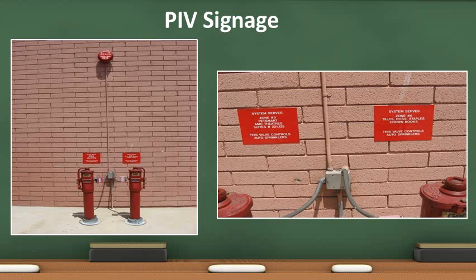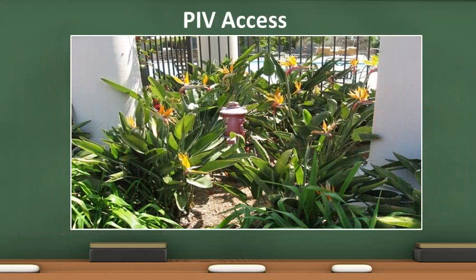In these photos, the signage indicating the buildings served is appropriately placed. Also note the sprinkler bell in the photo on the left. It is properly labeled with the type of alarm and instructions to call 911 when sounding. Note that three feet of clearance is required to all sprinkler system components. This PIV is obstructed and the vegetation will need to be removed.